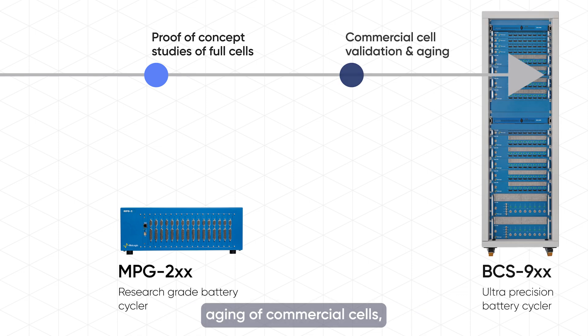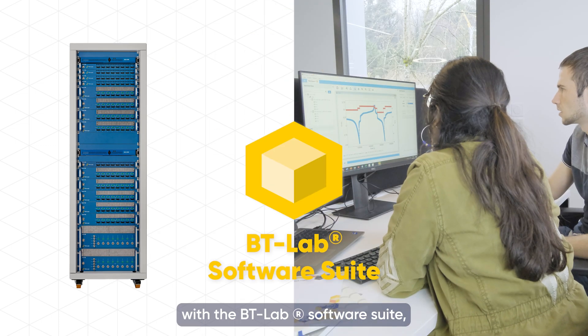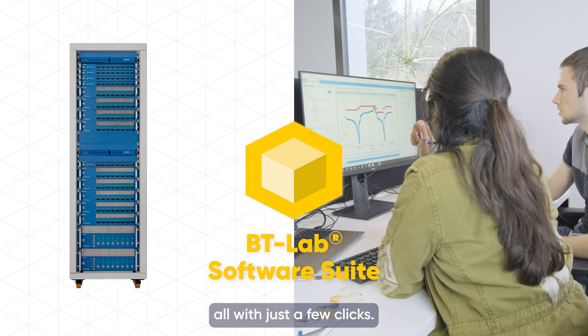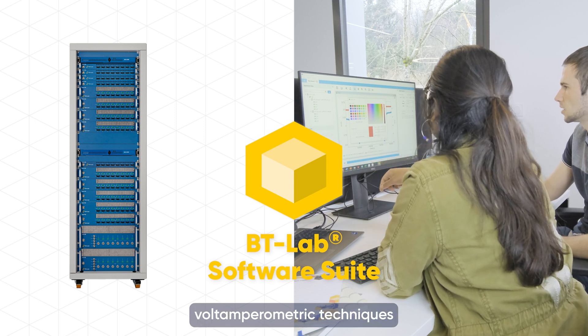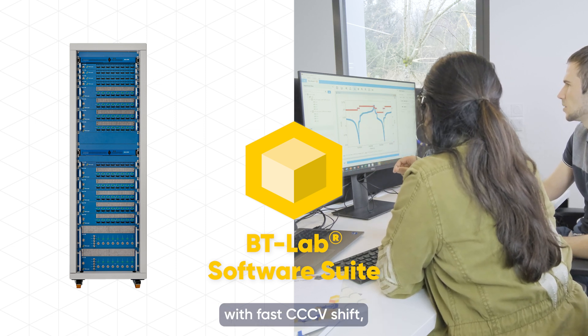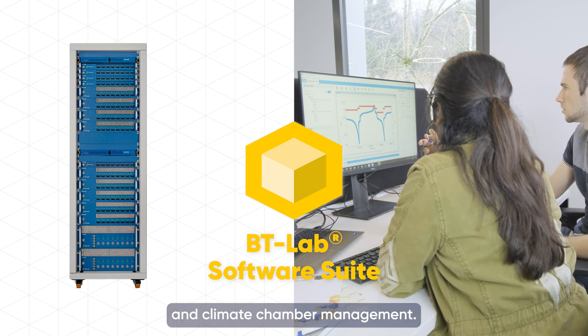For validation and aging of commercial cells, the modularity of Biologic's ultra-precision BCS900 series battery cyclers ensures the perfect fit according to specific needs. Design, setup, and execute test plans remotely with BT-Lab's software suite, all with just a few clicks. These cyclers offer voltamperometric techniques with fast CC-CV shift, EIS up to 10 kHz, and climate chamber management.